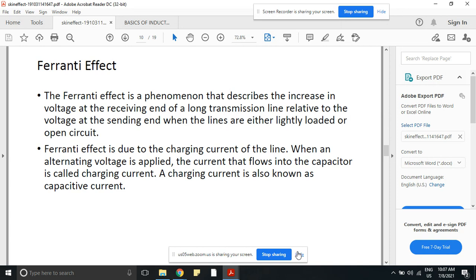But where is this Ferranti effect observed? This phenomenon is observed only in long transmission lines when they are lightly loaded. That means on the receiving end, no load is connected, or it is a lightly loaded case, not heavily loaded. In such a scenario, we can observe this Ferranti effect.